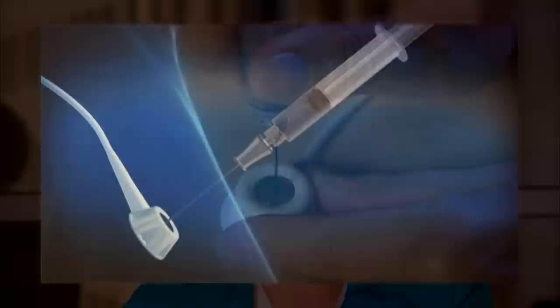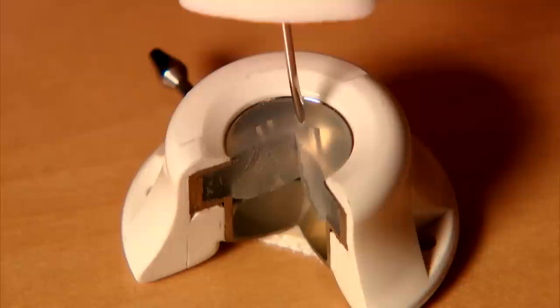After some investigation at the hospital side, they determined that they didn't think the problem was with the lap band, but rather with the Huber needle that's used to inject saline into the lap band. Huber needles have been around since about 1946 when the patent was first issued. Huber needles are designed so that when the needle pierces a rubber septum, there is no hole left behind — the hole, in a sense, heals back up as the needle comes out. That's important if you're trying to maintain sterility or if you have a need for multiple punctures through a port with no leakage after the fact.